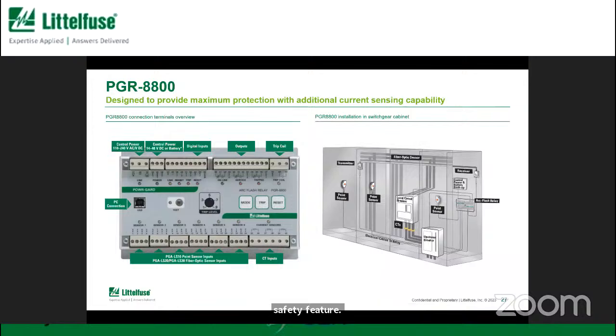Okay, so just a little bit on each type of relay. And I could spend an hour talking about each one, but I just want to highlight 1 or 2 differentiators between each product. And then, of course, we'd be happy to talk in more detail if you have questions about each relay. So the PGR 8800, that's starting at the top of the chain. So this relay has the most functions available. And this one has input for 6 sensors. Now, if you have more than 6, you can use multiple PGR 8800 relays together, connect them together, and then it'll operate as one group.